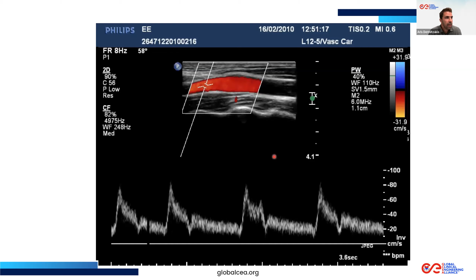This is the triplex. Finally, in ultrasound we can also use ultrasound contrast agents. Why do we use them? Because we have very weak reflections of ultrasound coming from the blood. It is 60 dB smaller than the tissue. So we use microbubbles. These are small bubbles that contain gas, about 3 micrometers, which can oscillate and break when insonified. These are filled with air, so we have very good signal coming back, and we are able to even detect blood flow in microcirculation.